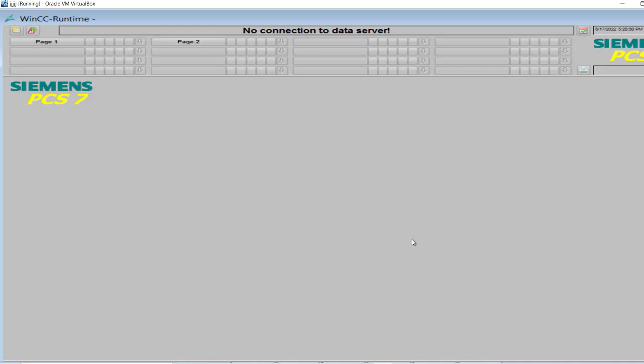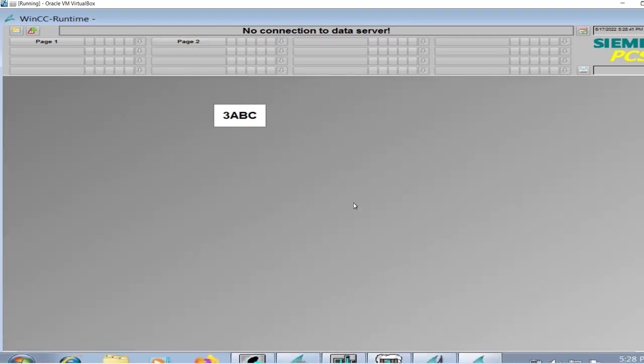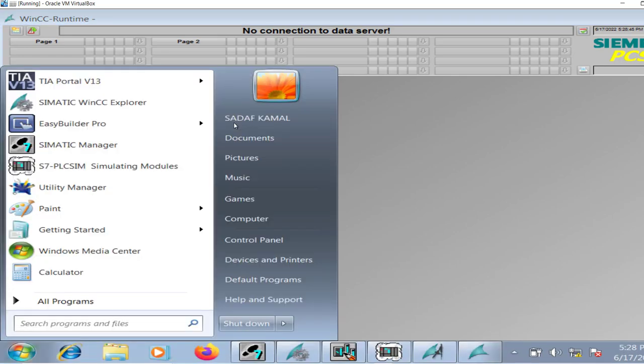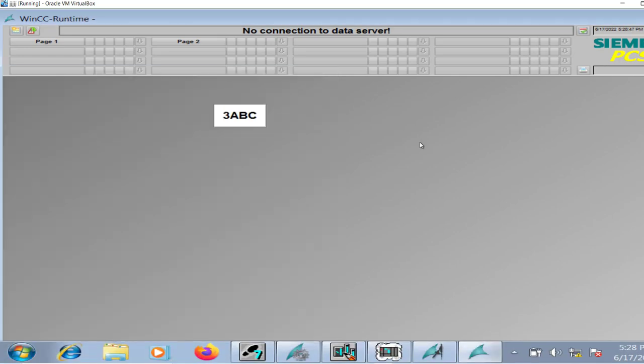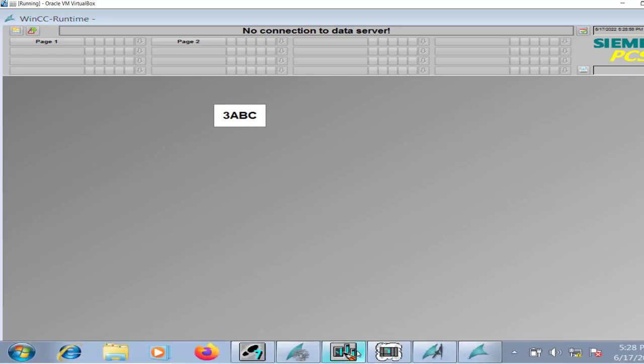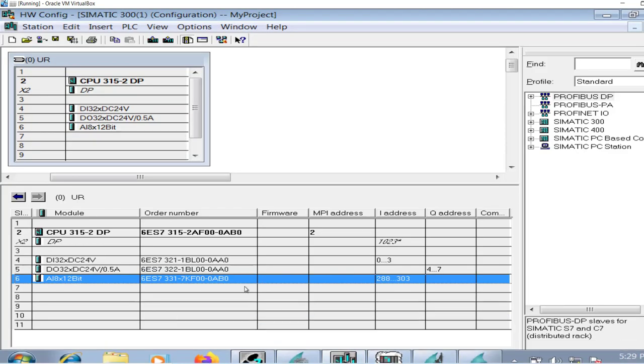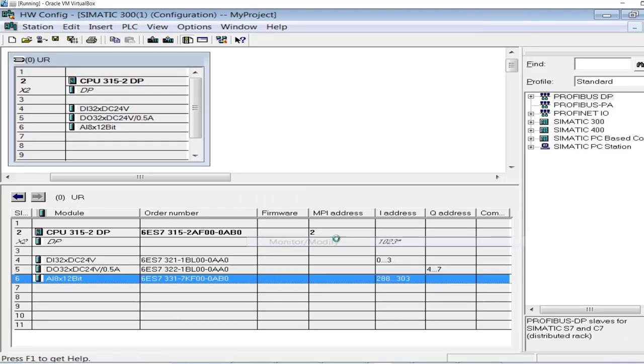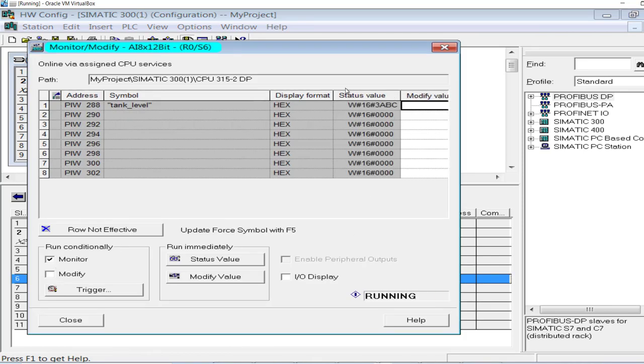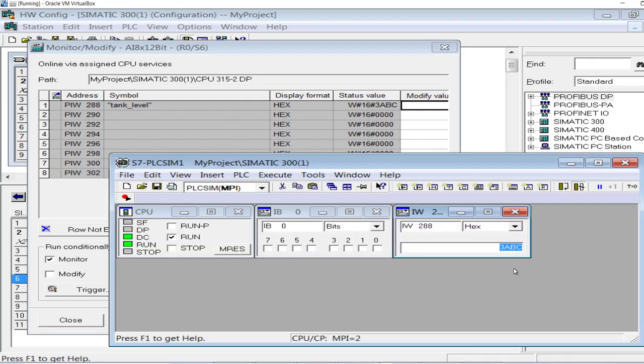To look into the status of the analog tag: 3ABC. From the simulator I have set this value as 3ABC. If you have the actual physical PLC, the value coming from the sensor through hardwire, the 4-20 milliampere would be displayed here. Let me go to the hardware configuration. In the hardware configuration, monitor the status.